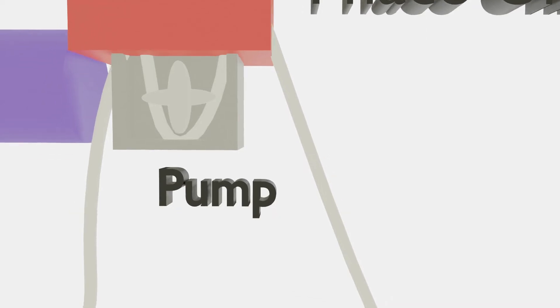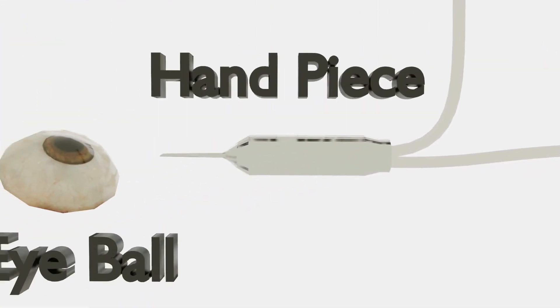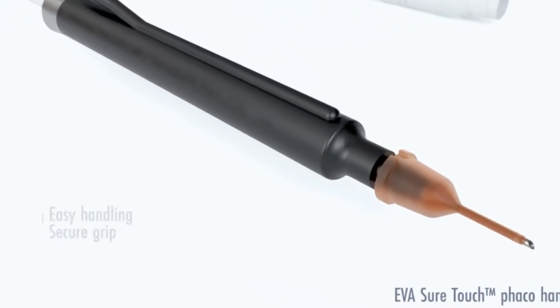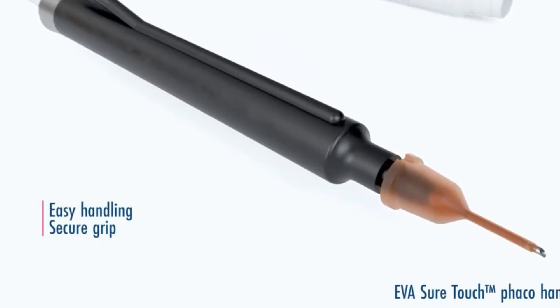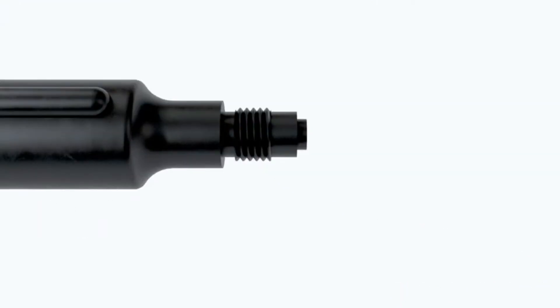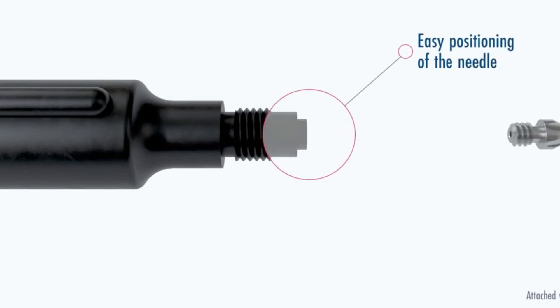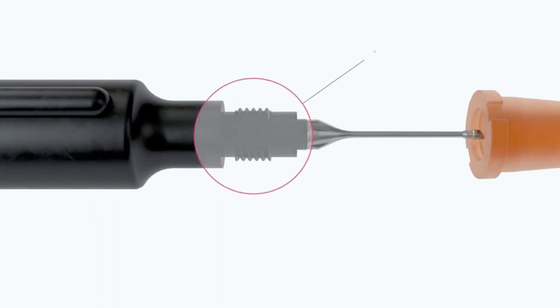The fourth component is the handpiece. The phaco handpiece is an ultrasonic handpiece designed to facilitate removal of the natural lens during cataract surgery. Using longitudinal vibrations, it moves at an ultrasonic frequency to emulsify the cataract and aspirate the debris through the hollow needle.